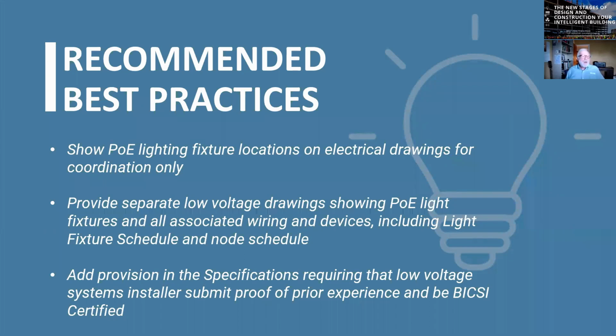So on the typical Division 26 drawings, we recommend just showing the light fixture locations for coordination on the electrical drawings. Then pull together all of the low voltage in a separate group. For example, typically the E1 series would be power. Some people make it lighting, but for our discussion, E1's power, E2's lighting, E3's one lines and riser diagrams, E4 schedules, and so on.